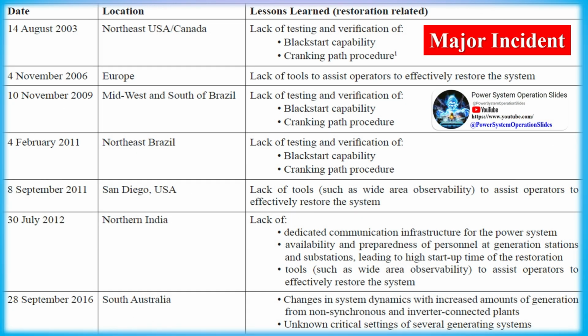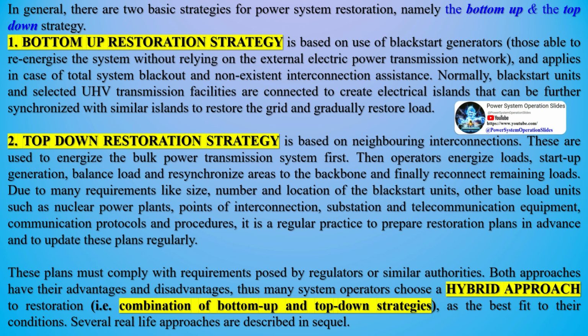Advantages of bottom-up. The advantage of the bottom-up strategy is that it enables power system restoration also when the top-down restoration is not possible. Disadvantages of bottom-up. The disadvantage is, however, that a black start generator or other similar voltage source within the power system is required. In addition, the management of the extremely weak network may make the bottom-up restoration more complex and slower to execute than top-down strategy.